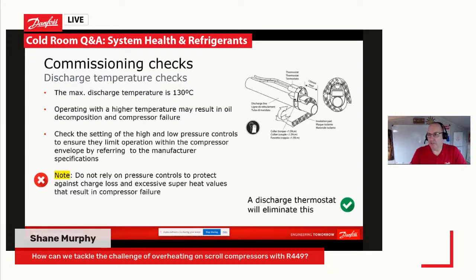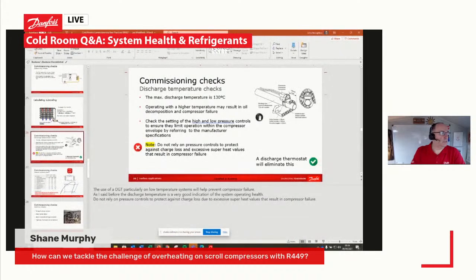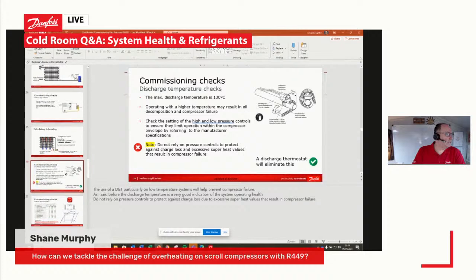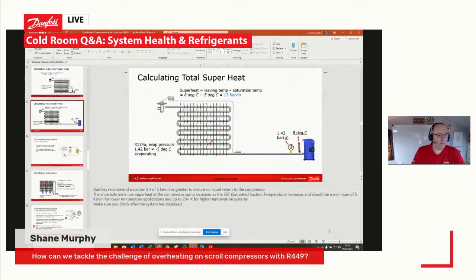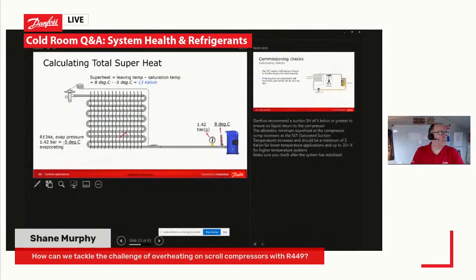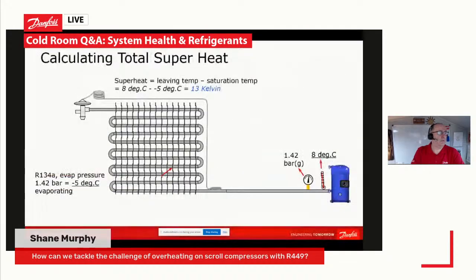The other thing to say is obviously make sure that we're measuring our suction superheat correctly, because that has a huge influence on the discharge temperature of our compressor. And I'm just going to put another picture up in a second, which is that one. Let's go full screen again and just swap it around. So there we go.